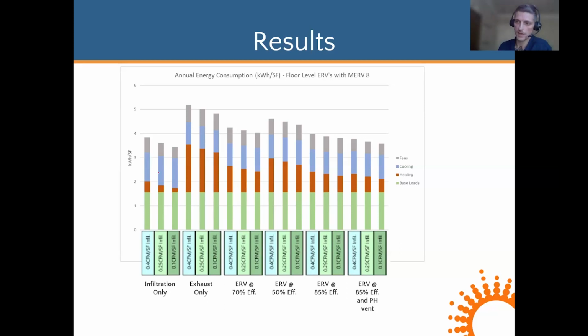In the infiltration only scenario, we see higher cooling load and lower heating because we're not dumping cold outside air into the space. The rest of these show our energy penalty for ventilating. The exhaust only is the highest consumption here. We have a lot of untempered air being dumped into the space and quite a high fan power for the rooftop exhausts. The ERVs are next lowest, with a reduction. We can see a reduction as the effectiveness of the ERV increases: 50%, 70%, 85%. And then as we reduce the airflow rates, this obviously increased our savings more. But this is just looking at total energy.